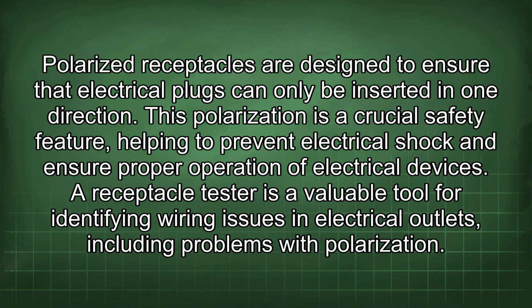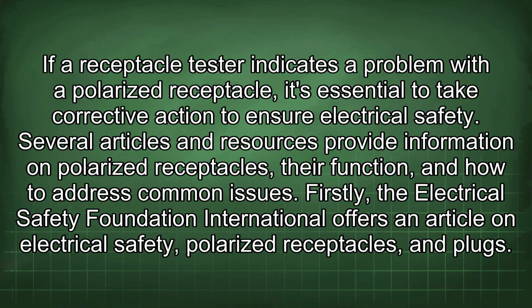Polarized receptacles are designed to ensure that electrical plugs can only be inserted in one direction. This polarization is a crucial safety feature, helping to prevent electrical shock and ensure proper operation of electrical devices. A receptacle tester is a valuable tool for identifying wiring issues in electrical outlets, including problems with polarization.